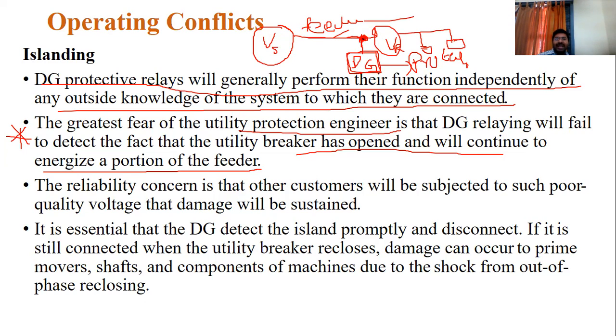Here our problem, the islanding problem, means that if there is a fault in this feeder, the feeder relaying equipment, reclosers and circuit breakers will detect that fault and clear the fault, nothing but to open that fault. So circuit breakers are open, so that may clear the fault. But in these situations also, DG protective relays may fail to operate. What will happen here in that case? This DG will not be separated from this line, so this DG will not be separated from this load.